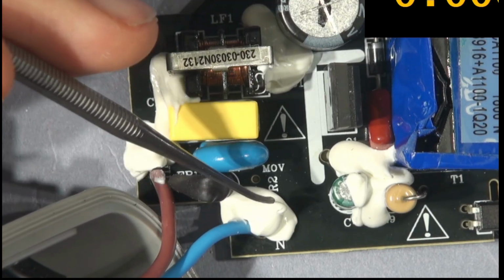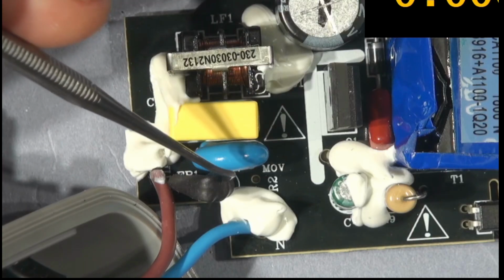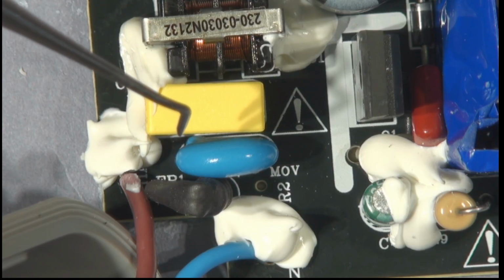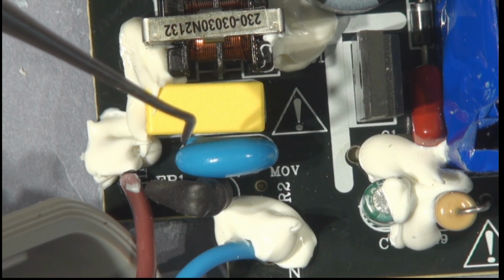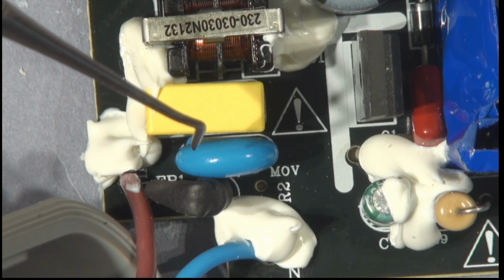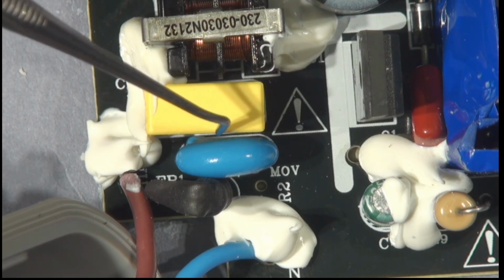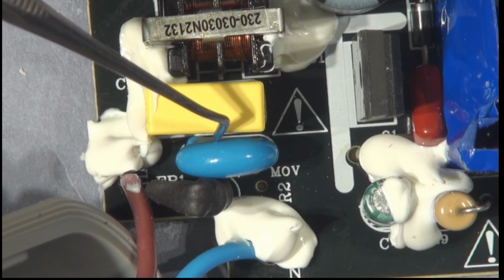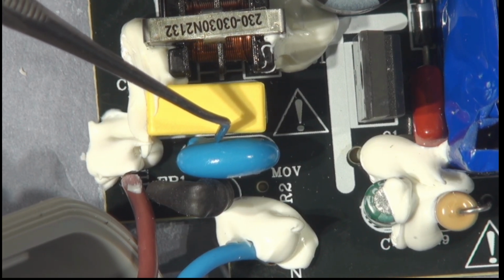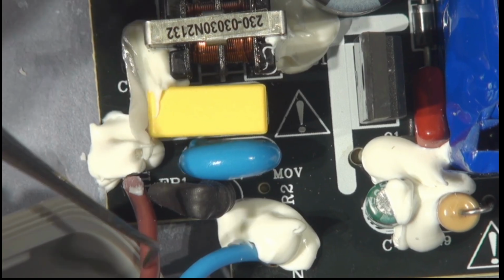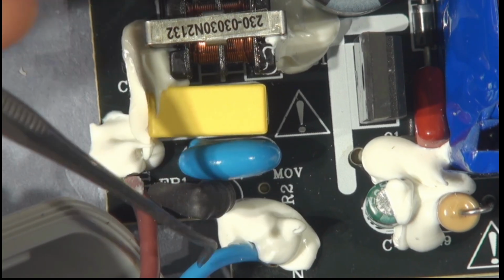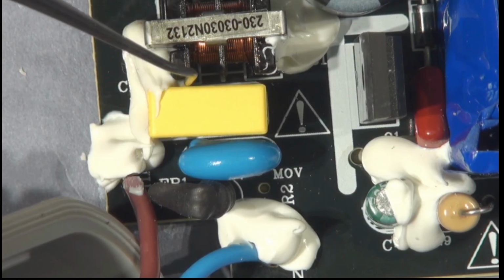If you plug one of these battery chargers in at the end of a long extension lead, they've got amps onto a generator, and if the generator regulator or governor goes wild, you get mad voltages, and these things just burn out - they can't take much. Therefore, very short term, sub 250 millisecond surges are conducted away between live and neutral, basically clamping the voltage across the input to the unit.